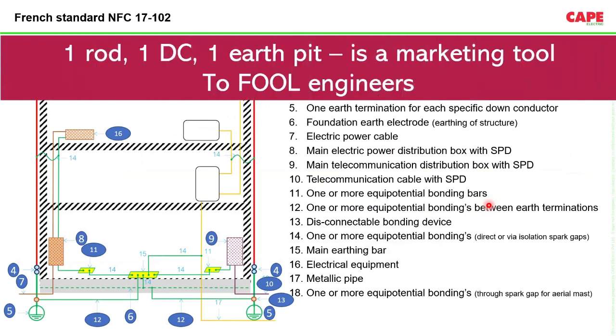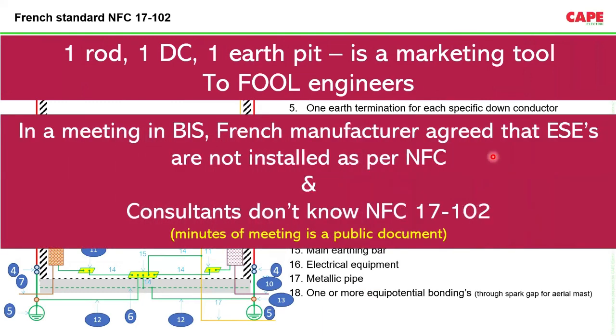So one rod, one down conductor, and one earth pit is a marketing tool, and this marketing tool is actually fooling engineers. All engineers are made fools, because if we know how a high frequency current works, then you will not accept this one down conductor principle. Also, there was a big fight in the market regarding this non-standard lightning protection. In a meeting in BIS, a delegation from France and from Australia came. There was a meeting held. Those documents are available in the public domain.